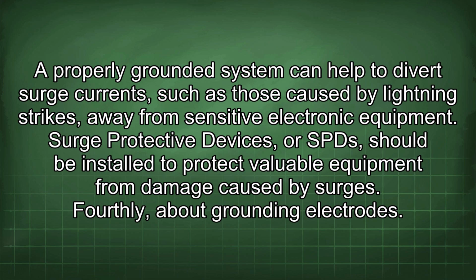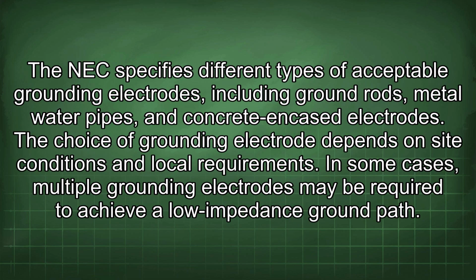Fourthly, about grounding electrodes. The NEC specifies different types of acceptable grounding electrodes, including ground rods, metal water pipes, and concrete encased electrodes. The choice of grounding electrode depends on site conditions and local requirements. In some cases, multiple grounding electrodes may be required to achieve a low-impedance ground path.